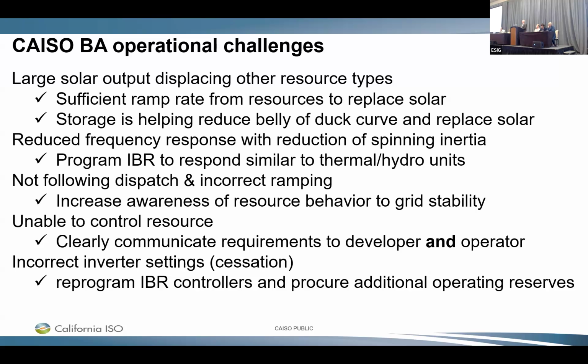We also had issues with cessation on some of the wind and solar. If there was a 500 or 230 kV line relay, the programming at the time, again more like a distribution system, was using the voltage to calculate a frequency, and it would see a frequency drop below its programming and actually shut down the plant. So we'd lose a line, and then unexpectedly, miles away, a plant would trip off or go to zero. They didn't even trip, the breakers were still closed, but they stopped producing. So we got them to reprogram the controllers for that as well.